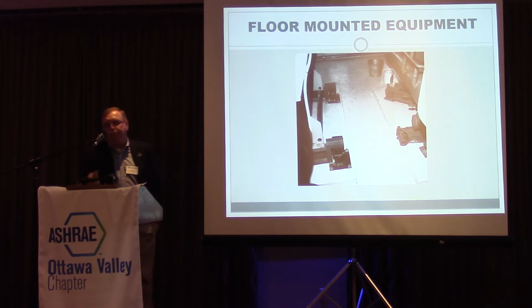This is one of my real pet peeves, and that's why I chair ASHRAE's Standards Committee for testing of vibration isolation for seismic restraints—it's to get rid of junk like this in the field. You've got people selling unscrupulously, telling you anything you want to hear: yes, this can handle the California hospital, no problem. Any decent engineer worth his salt could look at this and say there's no way in hell, unless you're only putting 100 pounds on it, that it's ever going to hold up a chiller.